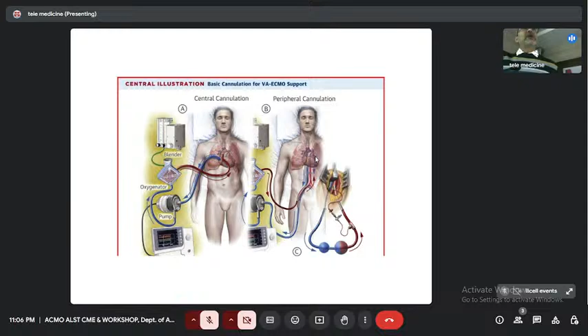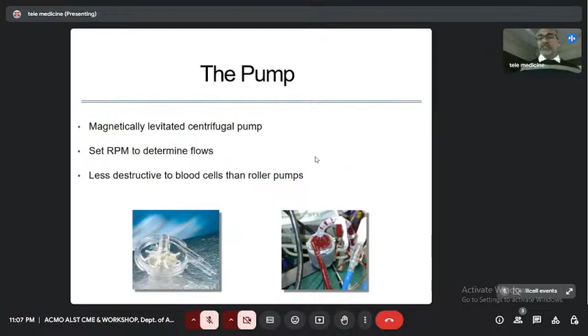For the pump of the ECMO machines, if you have CRRT machines, I'm sure you must have seen the roller pumps. Roller pumps are not used for ECMO machines because in ECMO you have to go with very high flows of like 3 to 7 liters. That's the kind of flow you want to aim at for good oxygenation. So we normally go for centrifugal pumps in ECMO machines. They are associated with less destruction of blood cells, so lesser hemolysis, and they help the hemodynamics in a better way.